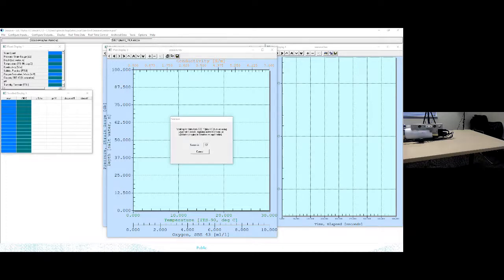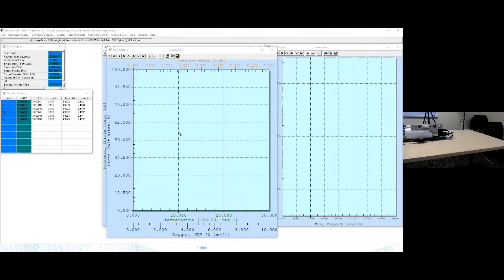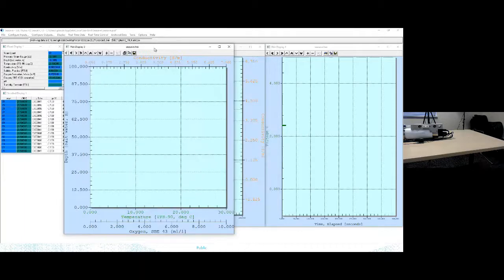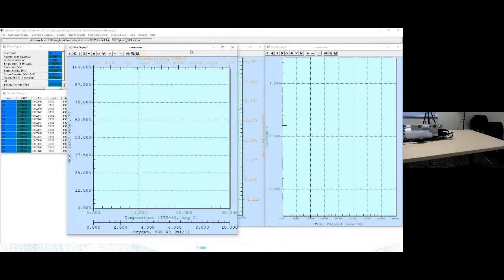Now, this is a countdown timer saying Seasave is waiting to get data from your CTD. In this case, my CTD isn't outputting anything until I click the switch to on, at which point it's going to start outputting some data. Once that countdown timer goes away, then the data is being received by Seasave. And as long as your XMLCon file is able to interpret that data, you'll start to see that coming in. So in this case, I have a scroll display that's showing all of the samples that are coming in from my CTD. And in my plot displays here, I can see the data coming in.